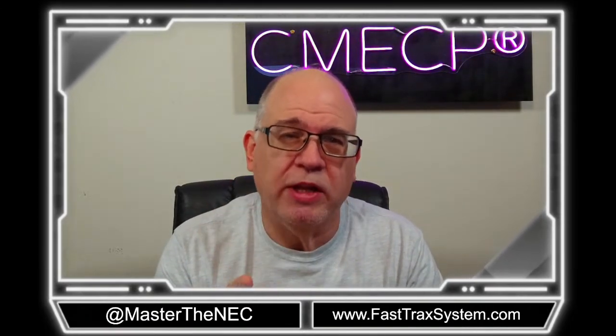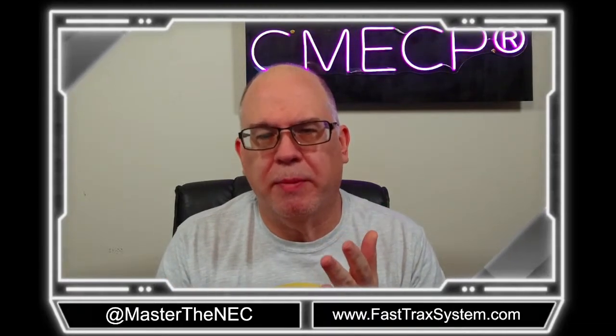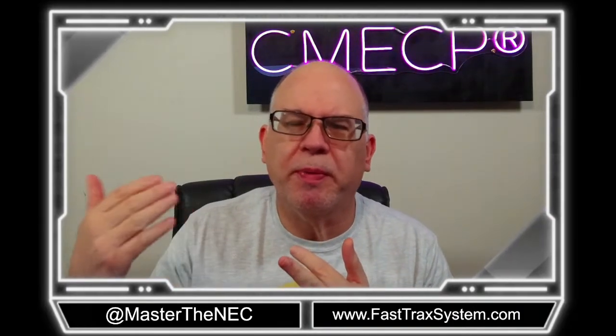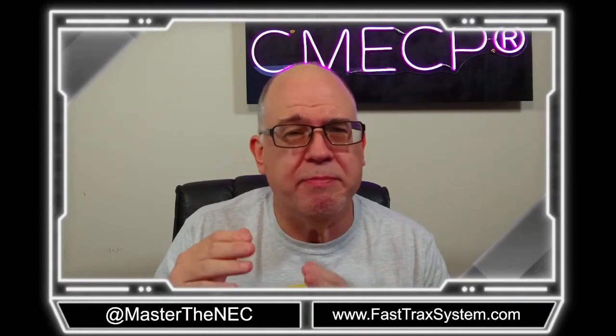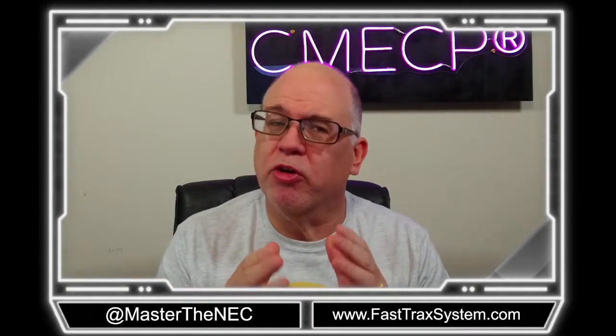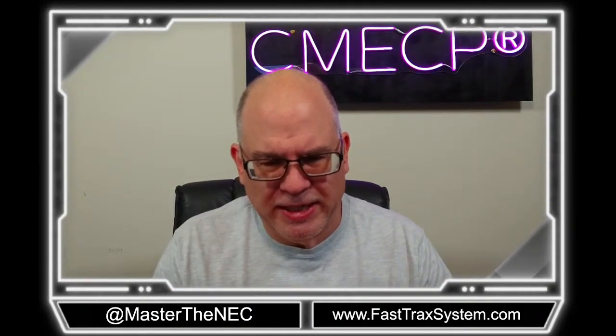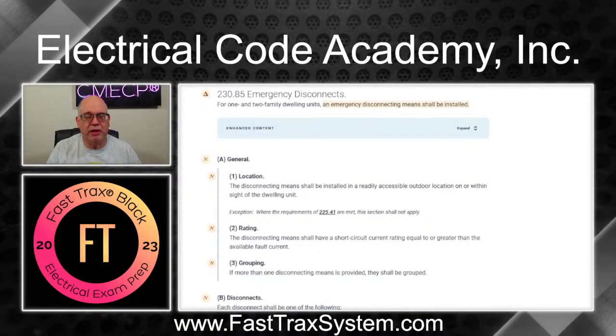The 2023 edition of the NEC expanded things a little bit — added a replacement requirement, some marking requirements, and a little clarification. If you have other power sources such as PV or a generator and their disconnect is somewhere else not grouped with the emergency disconnect location, then you're going to have to put a placard or directory telling people where that is. So we want to make sure we keep all those things in perspective. Let's go to the National Electrical Code.